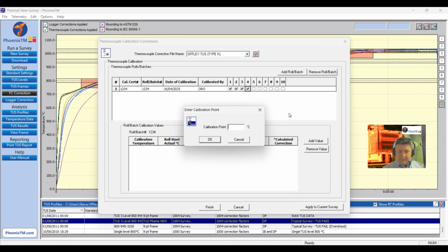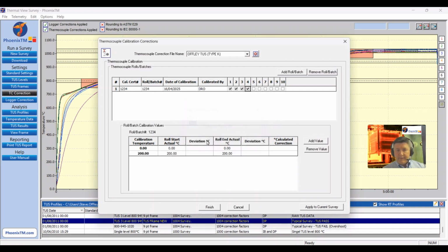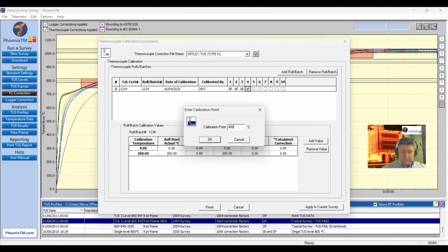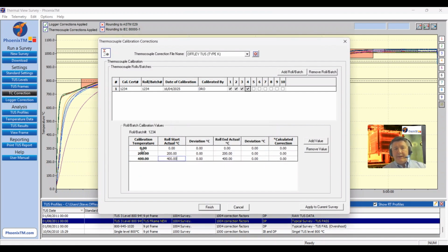So I've got 0, add value, 200, add value, 400. Obviously these temperatures would be matching what's on the calibration certificate. I would then put in the actual roll start values and the roll end, and it would then automatically calculate it. So for instance, just to show you how that would work, I'm going to say that the actual temperature at 200 is 200.1, both start and stop, and you can see here that that would then generate a calculated correction factor applied to the TUS data at 200 of minus 0.10 degrees Celsius. Okay, I'm going to add another batch.